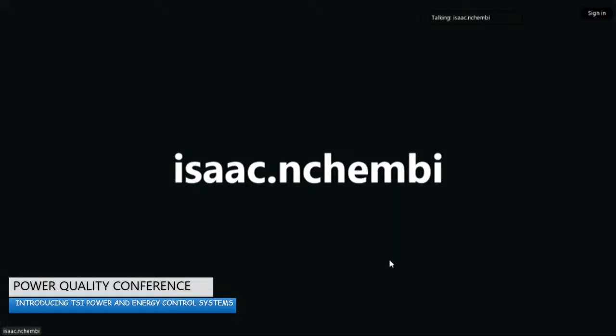what VRP can offer and what it can resolve from the cases we are facing as challenges. So I got to them with two points: the low voltage issue would be resolved, and the cost we are incurring on running the branches on generator would be reduced or omitted. So the bank will be saving a lot of money. Instead of using the generator during periods of low voltage, the VRP will be able to stabilize the voltage, and the bank will save a lot of money on costs instead of using the generator, which is costing us on fuel.